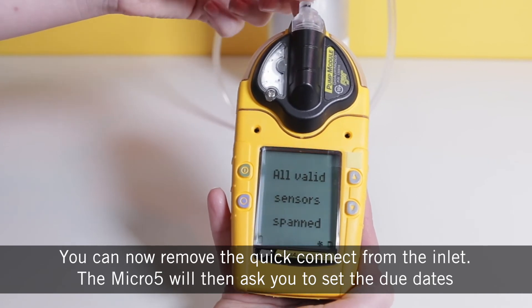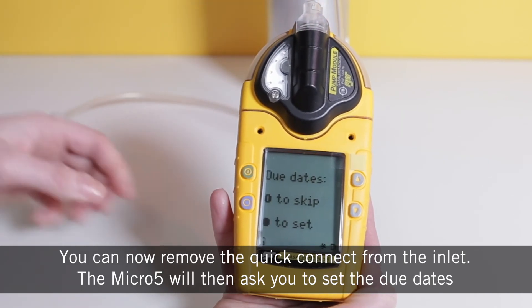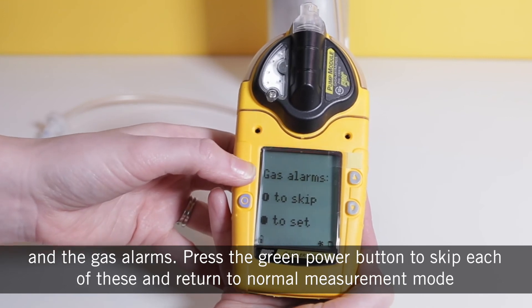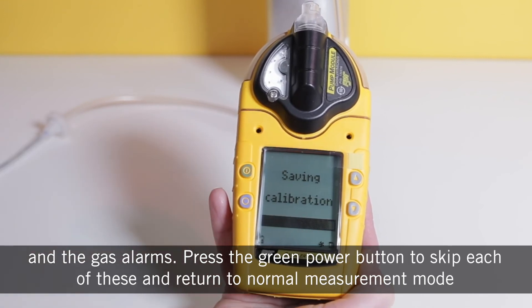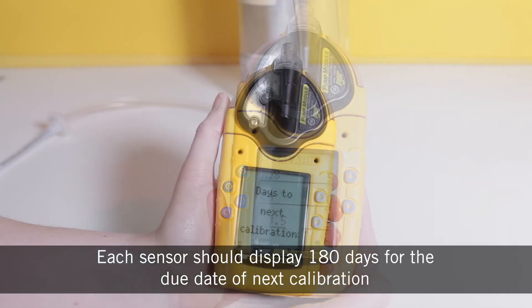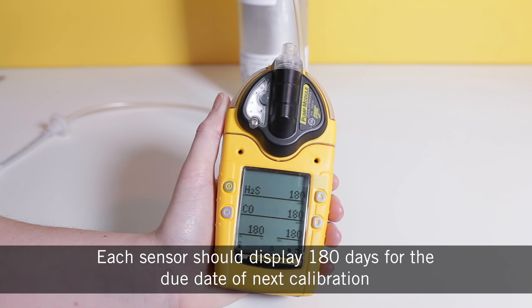You can now remove the quick connect from the inlet. The Micro5 will then ask you to set the due dates and the gas alarms. Press the green power button to skip each of these and return to normal measurement mode. Each sensor should now display 180 days for the due date of the next calibration.